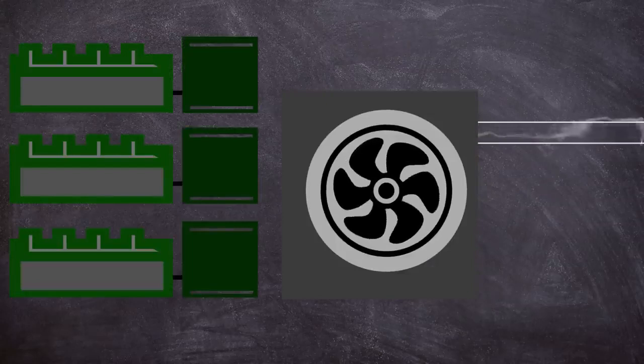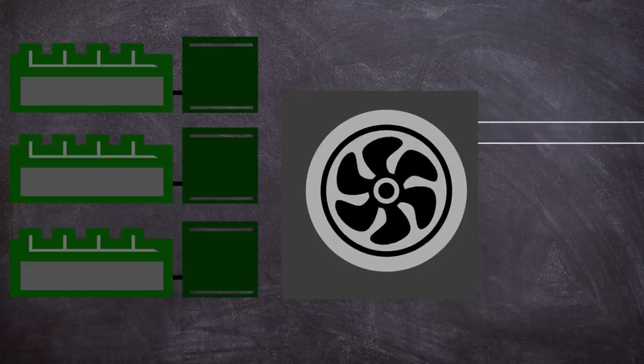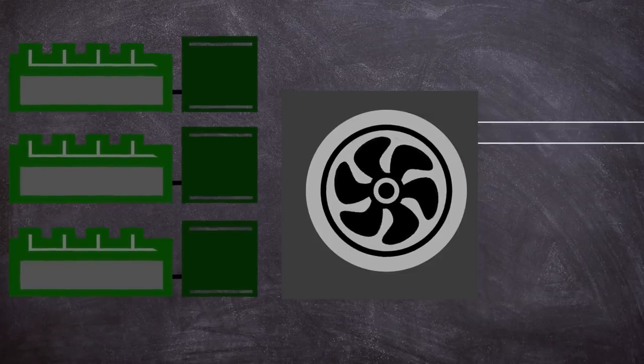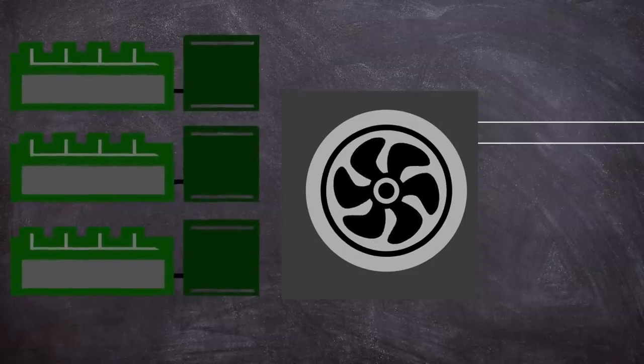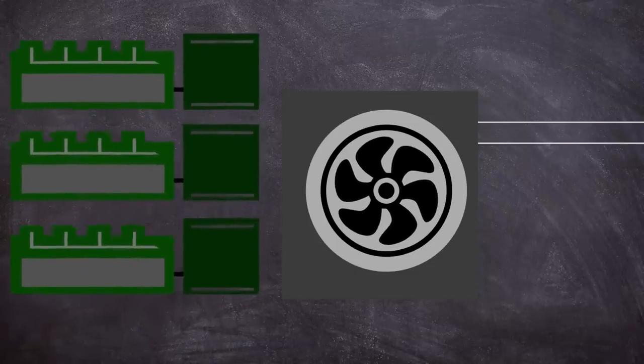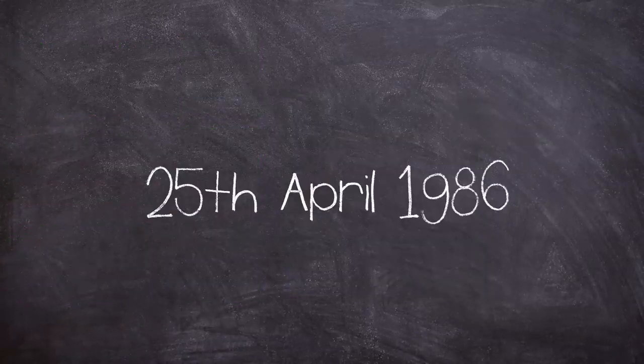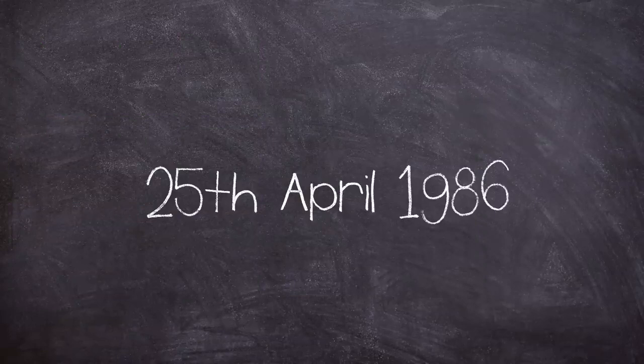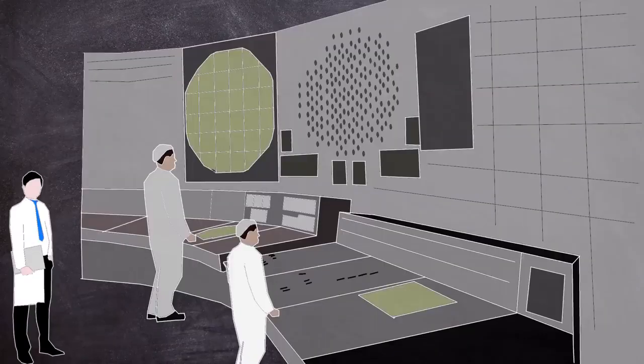In preparation for the test, the reactor power was to be reduced to between 700 and 1000 megawatts of thermal energy, and the steam turbine generator was to be at normal operating speed. After this was sorted, preparations for the electrical test could go ahead. The steam supply to the turbine generator would be closed off, and turbine generator performance would be monitored to see if it could bridge the power for coolant pumps until the emergency diesel generators took over. When the emergency generators supply power, the turbine generator would be allowed to continue freewheeling down, then normal planned shutdown procedure was to be completed. The date of the test was the 25th of April 1986, 15 minutes past 2pm, completed by the day shift.